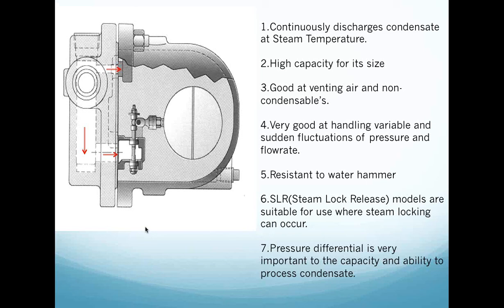If you have to lift condensate to an overhead return header or to an overhead receiver, I want you to know, because I'm a pump guy also, and I sell, size, and help consult with pumping problems, that on the steam side, we can lift condensate 2 feet for every 1 pound of pressure. So if I had a 10-foot overhead return line that I had to get to, you'd have to have 5 pounds to get to that 10-foot overhead return elevation.